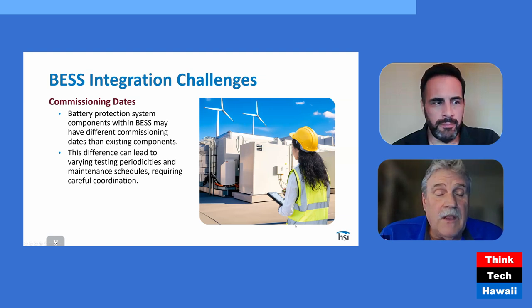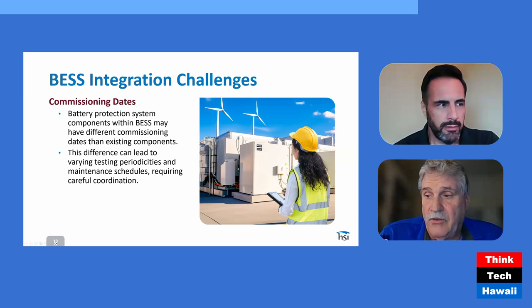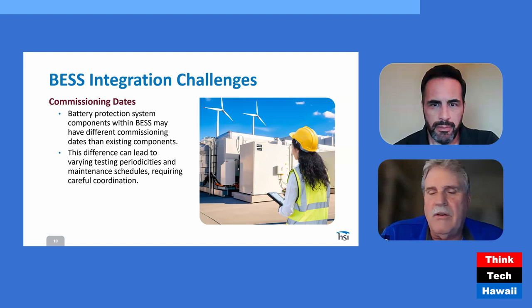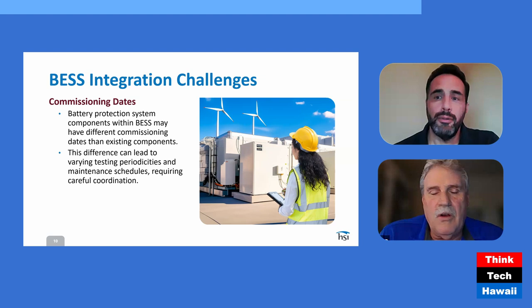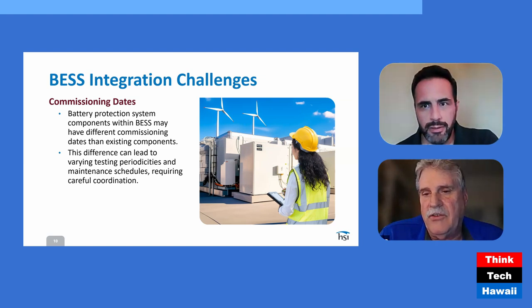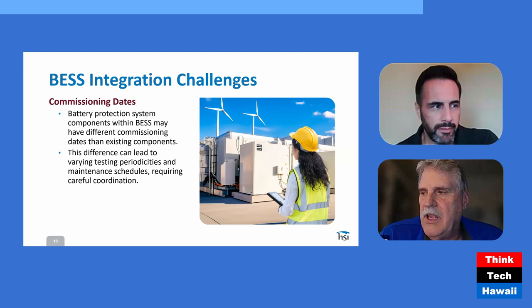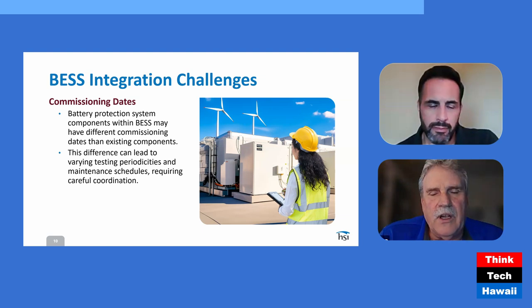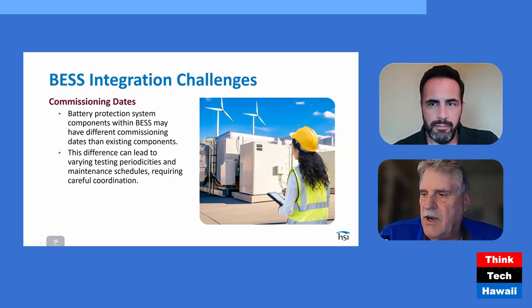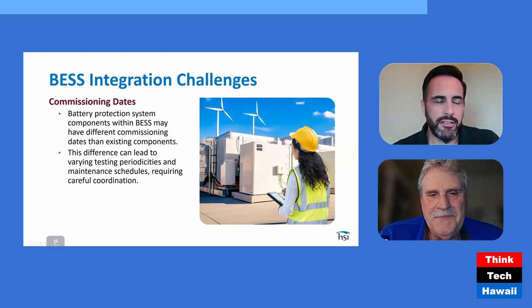Not to say that if you have a 6-year window and an existing generator you've had for 2 years, and you add a battery storage facility in year 3, it can fall within that window, and then you can test everything again in the next 3 years and have it all on the same schedule, which is what most people are doing. It just takes amending your procedures and changing the list of components, and making sure that change management process catches everything, and everybody gets notified, from contractors to operators. That's probably a much better way of doing it.